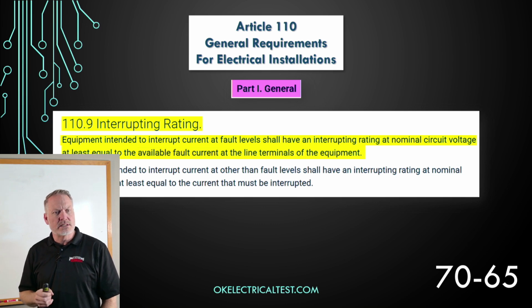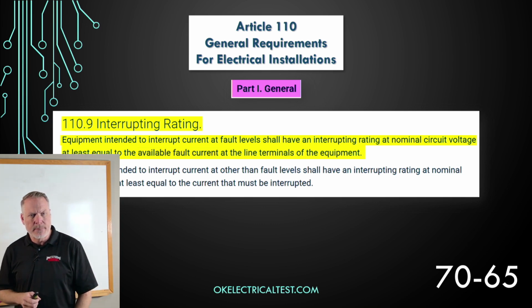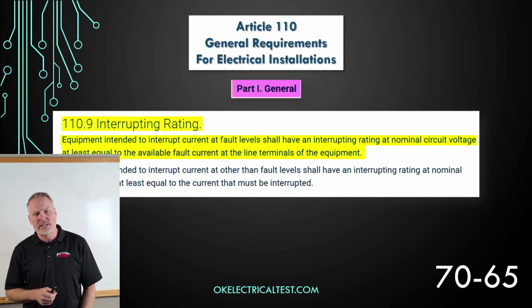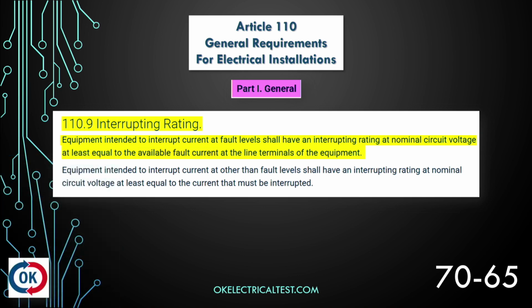And so we're going to go to 110.9, interrupting rating. And we're going to highlight: equipment intended to interrupt current at fault levels shall have an interrupting rating at the nominal circuit voltage at least equal to the available fault current at the line terminals of the equipment.